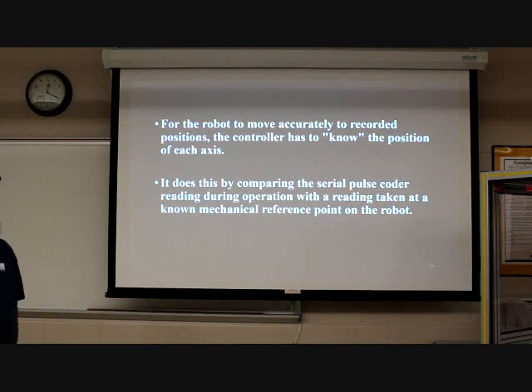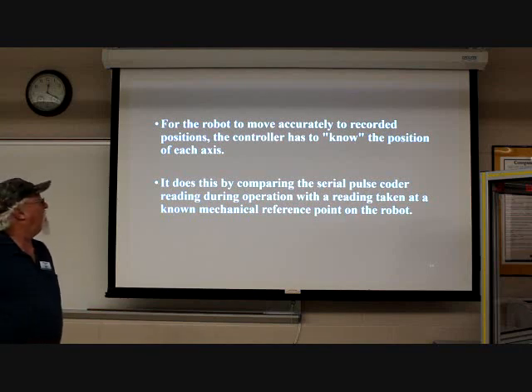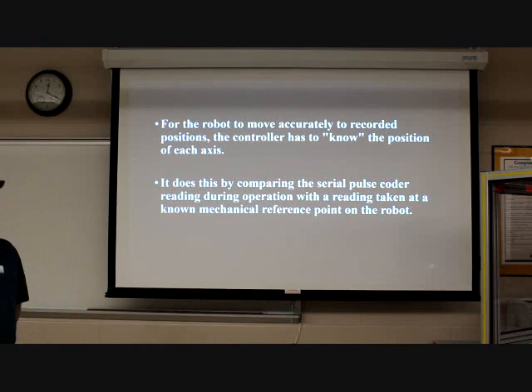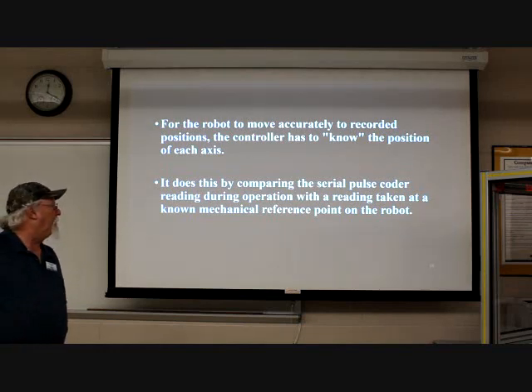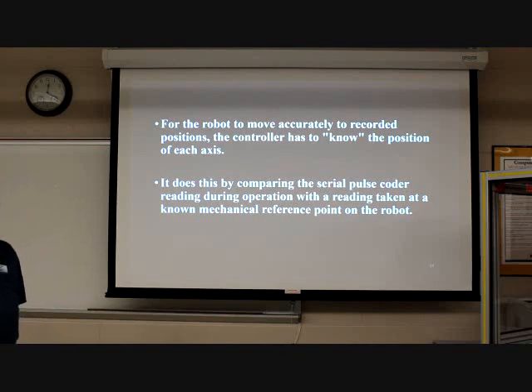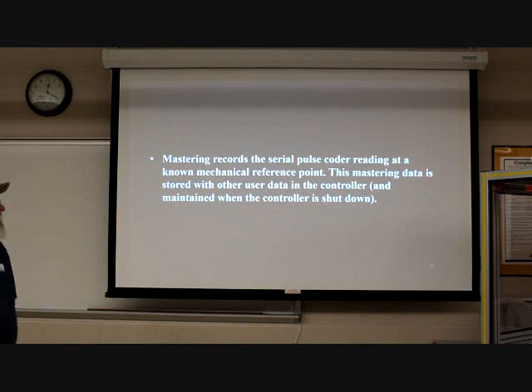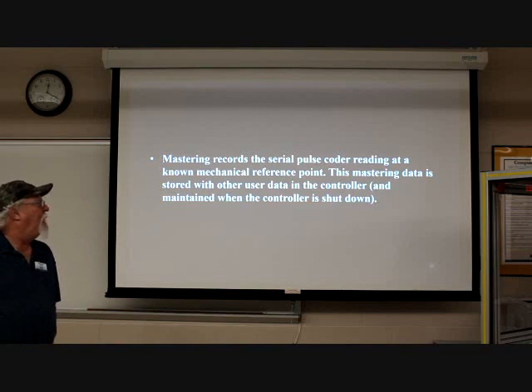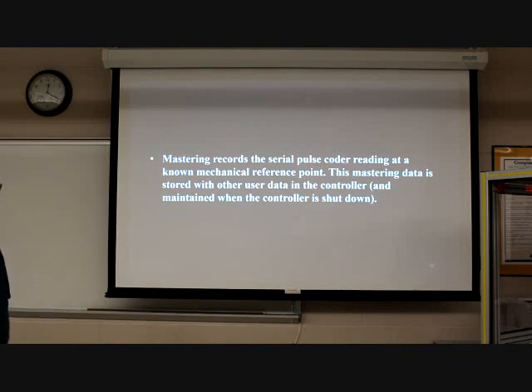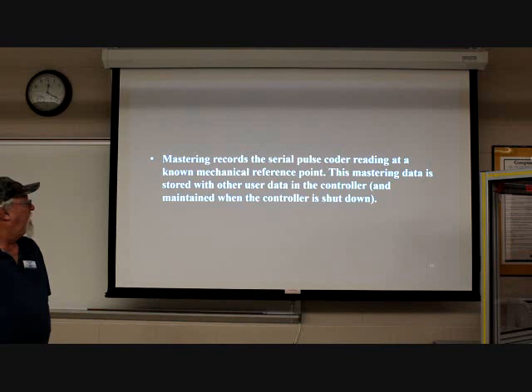For a robot to move accurately to record the positions, the controller has to know the position of each axis. It does this by comparing the serial pulse coder readings during operation with a reading taken at a known mechanical reference point on the robot. Mastering records a serial pulse coder reading at a known mechanical reference point. This mastering data is stored with other user data in the controller and maintained when the controller is shut down.